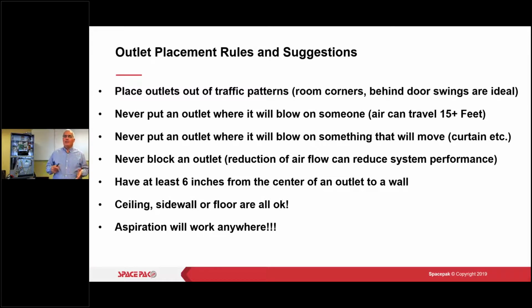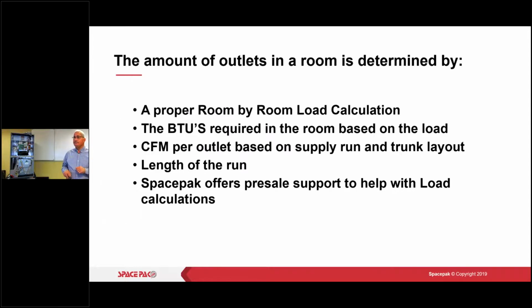All right, so we don't want to have curtains moving around. We don't want to block an outlet. So if you know there's going to be some furniture or obstacles in the way, you need to get that air blowing in a column fashion into that room. So be aware of that. This is probably the hardest part of figuring out where to put your outlets, right? So we don't have any blockages, all right? At least 6 inches from the center of an outlet to the wall, right? We can do ceilings or sidewalls, floors, all okay. It'll work anywhere. Again, placement's just critical.